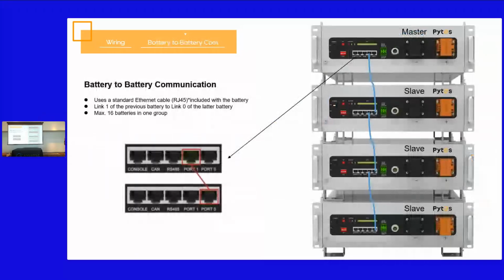Next is to connect the communication cable between the batteries. We use the standard Ethernet cable included in the battery package. The link order is Link 1 of the previous battery to Link 0 of the later battery. The first battery is the master battery, which communicates with the inverter. We can connect a maximum of 16 batteries in one group.